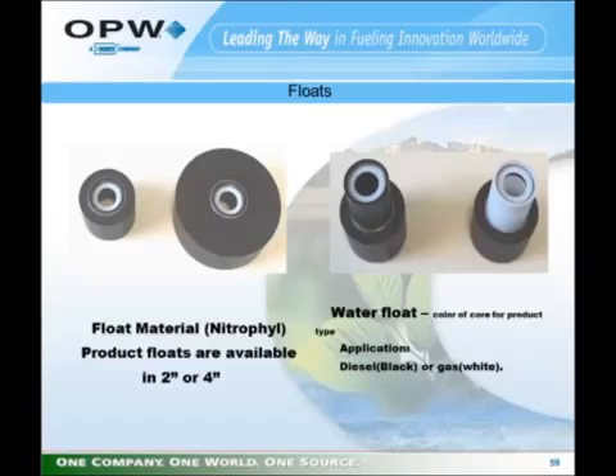So the product float is normally mounted on the probe with a magnet to the bottom of the float, and the water floats have the magnet at the top of the float. So care must be taken that those two magnets don't come into too close of a proximity with each other. If they do, the magnetic fields will merge and the system will see one float instead of two floats and generate a trouble code that indicates loss of signal.